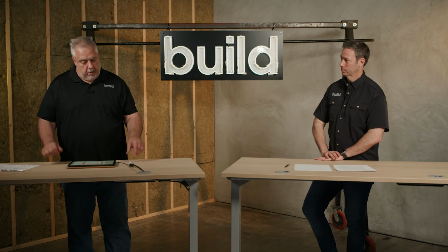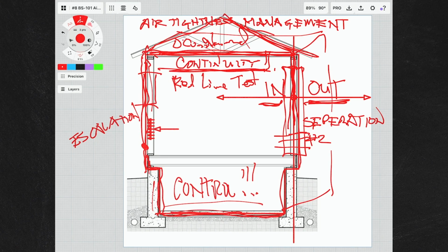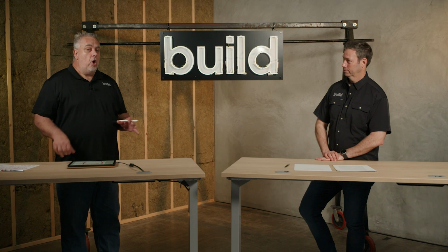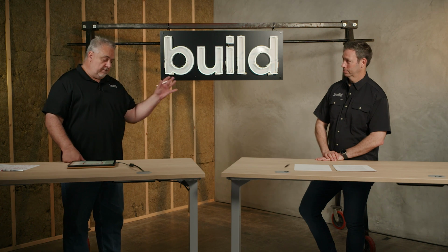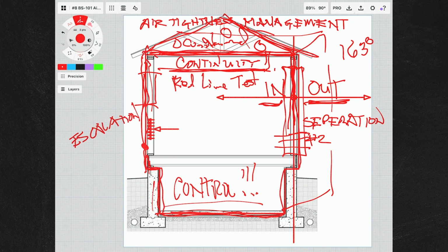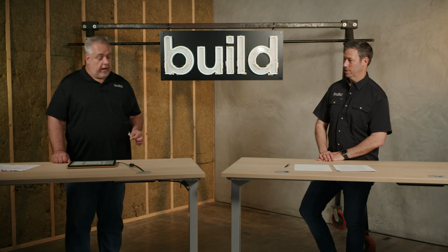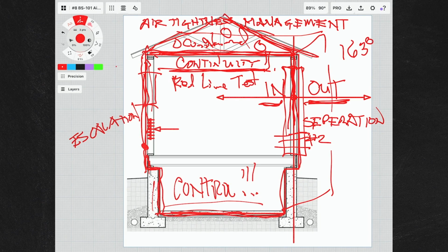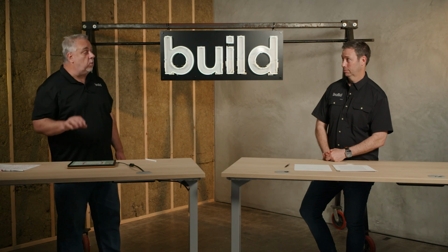All right. I stopped by a builder building his own dream house. This is the house they're going to carry me out of, Steve. Okay. I go in the house, and just as you say, there is ductwork, there is equipment up there, all that stuff. It's in Texas. We had just left another house, a building science friend of mine. We were doing some work in the attic. That day, we measured 163 degrees in the attic. Dang, that's hot. Outside, it was probably somewhere around 100. All right, so there was a huge delta. That attic was an oven.